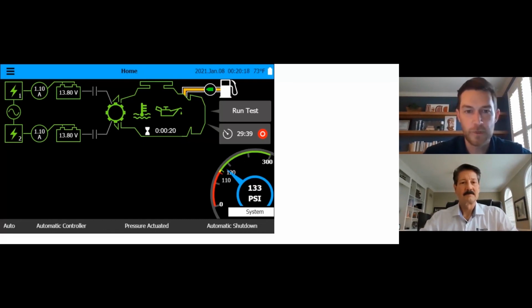Most people will just open up a valve, drop the pressure, and the pump kicks back on, because again you're on a closed system, so the pressure goes back up immediately, but it logs it as an auto start, which to the control panel, an auto start is a fire. And the way the system is designed, it's sacrificial equipment, so it's going to run nonstop until it thinks the fire is out or somebody stops it.